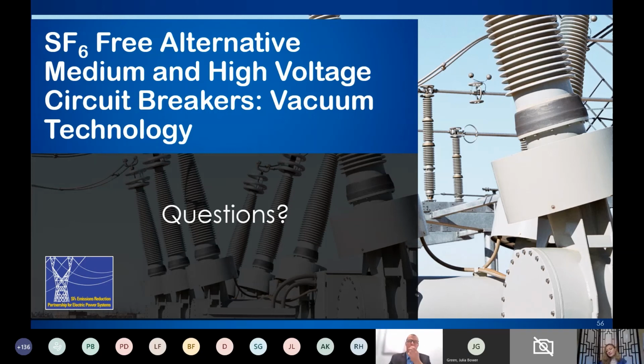This is Kyle, I can speak for PPL. Much of our distribution circuit breaker fleet is all vacuum right now, so 69 kV isn't essentially that much different. When we're commissioning an asset, each different manufacturer and type of breaker has a different commissioning form and acceptance criteria, so that's very clear and black and white as we're energizing and bringing something into service. During maintenance and troubleshooting, we have DDI specific to each type of equipment on our system. So if it's an SF6 circuit breaker, we'll get an SF6 troubleshooting sheet along with the DDI, which is your work method for how to troubleshoot, maintain, and repair it. So it's very similar to what we're doing for our vacuum circuit breaker, just carrying that methodology over from our distribution fleet to our transmission fleet as well. We don't have a large number on our system yet, but so far so good.